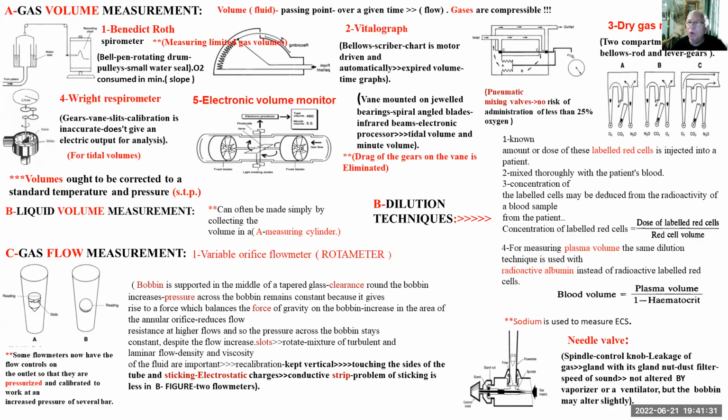First of all, we are going to discuss what we call gas volume measurement. We are going to discuss almost 6 points. This is the first point. What's the difference between volume and flow? Flow is the matter of volume per time. The problem of flow, of course, it could be a liquid or a gas, is that gases are compressible. Whenever they are compressible, they can yield fallacies.